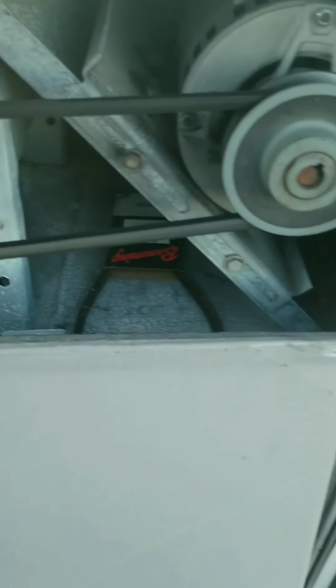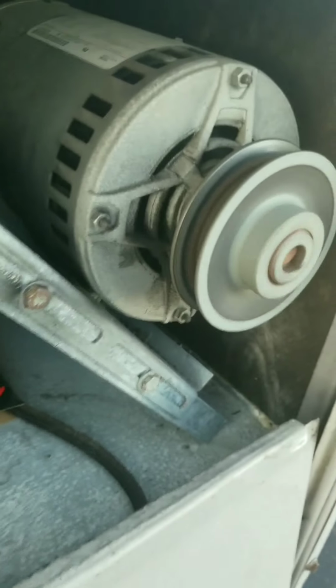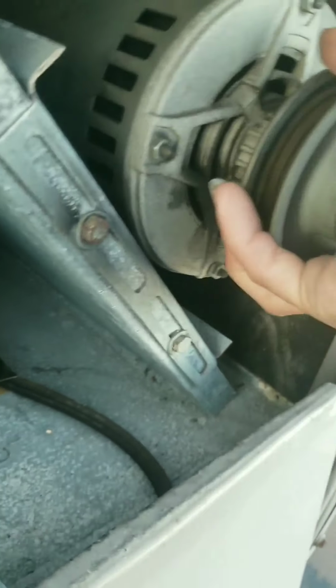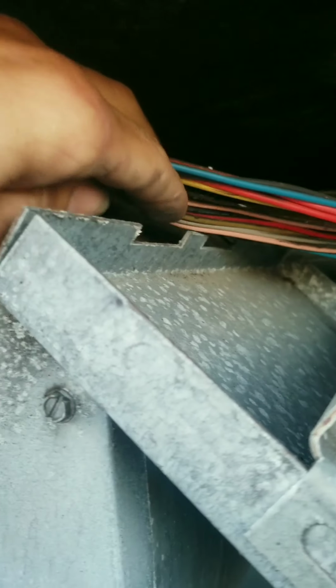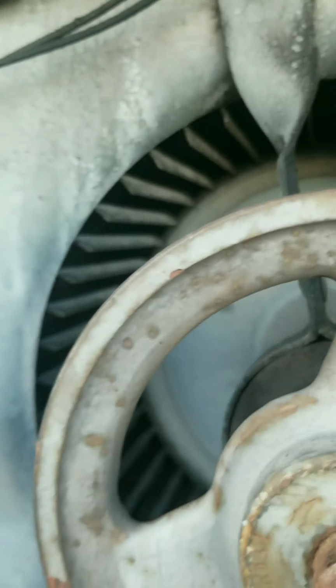They've over tightened that belt enough that they've killed the bearings in this motor. Yeah. Those bearings are shot. Feel too much play in those bearings, but always look for your rub outs right here on these corners of these carriers where they run these wires. If your wires sag enough, and then back there across those plates is all the typical rub out spots.